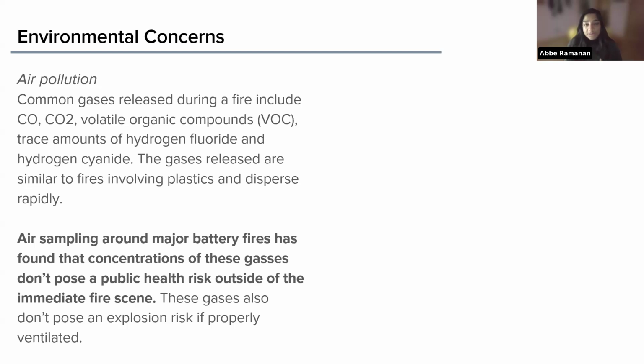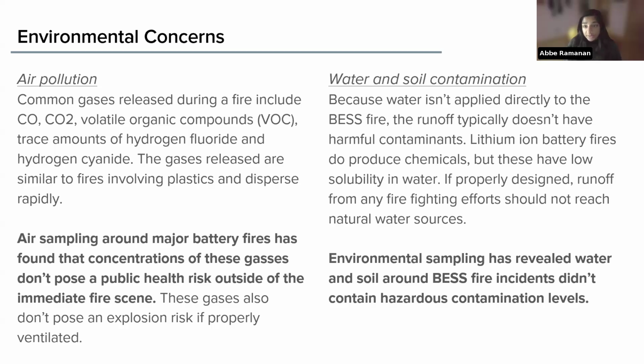In terms of water and soil contamination, good firefighting practices for battery storage fires involve not directly applying water to the fire, which helps minimize concerns around water runoff. Sites should also be designed to minimize water runoff into nearby bodies of water. Even if there is runoff, the chemicals created by lithium-ion battery fires have very low solubility in water, so there's not a huge concern of water or soil contamination. Extensive studies done after major battery storage fires, sampling soil and water after BESS fire incidents, have not found any high levels of hazardous contamination.